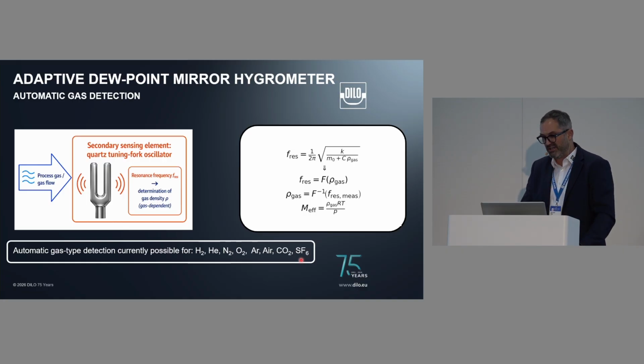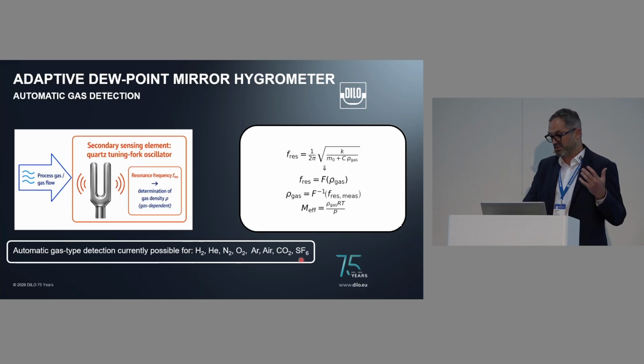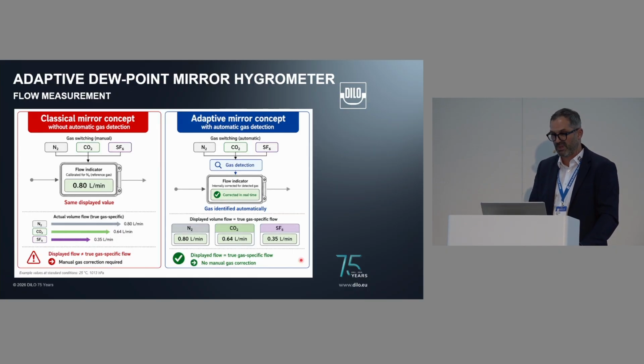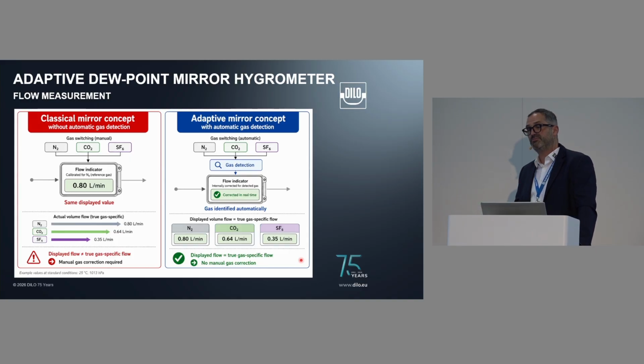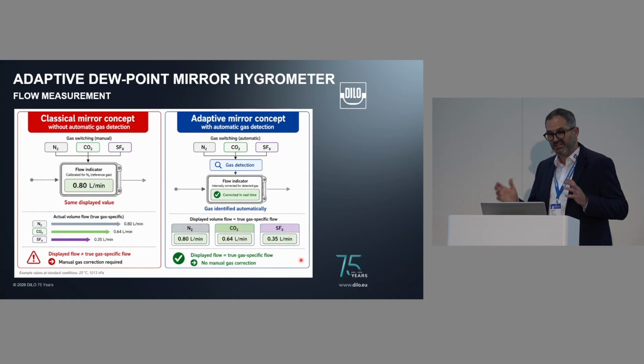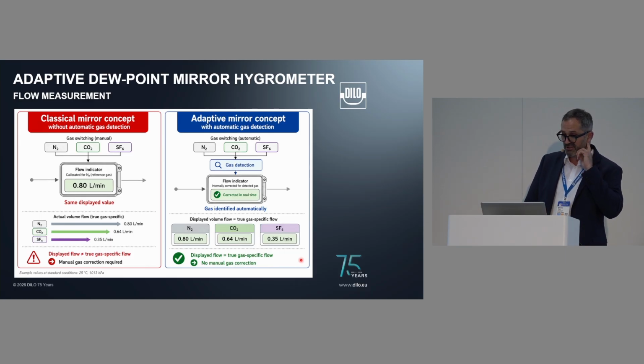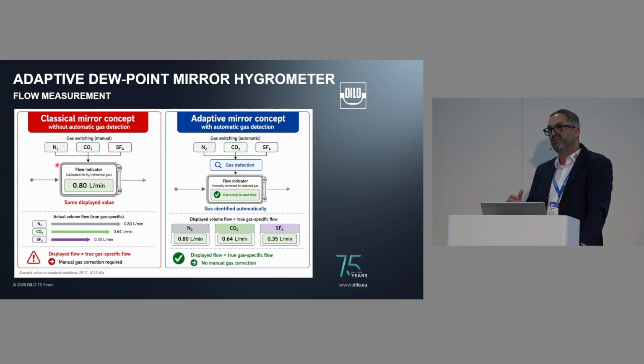So yeah, we have here our automatic gas detection, and we get a lot of advantages from it, which are particularly important for applications in industry. So for example, for a stable dew point measurement, you need a stable flow and a correct flow. You always have a range where your chilled mirror hygrometer or dew point hygrometer operates in a good way. And in a classical chilled mirror hygrometer, they are usually optimized for nitrogen or air. And for example, if you have a measurement in CO2 instead of nitrogen, then your flow sensor will show the value that is correct for nitrogen, but not for CO2.